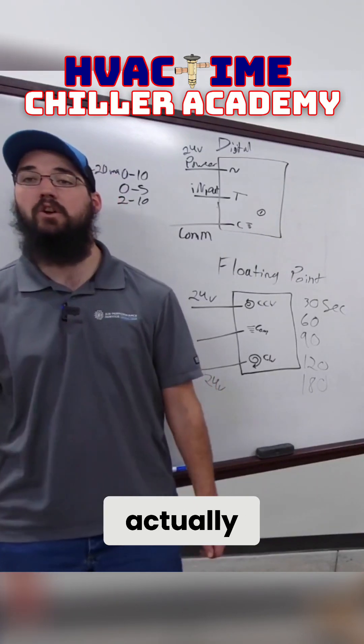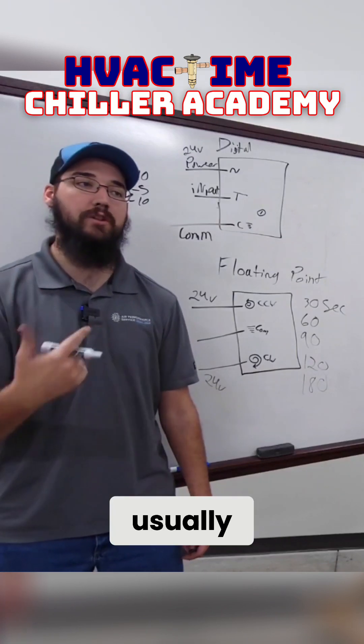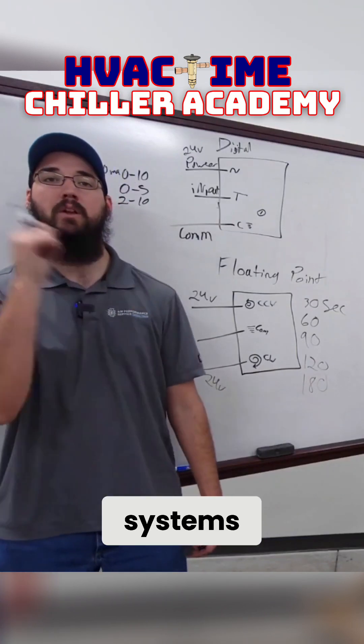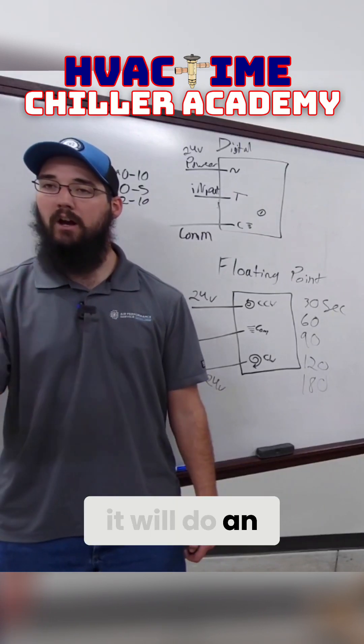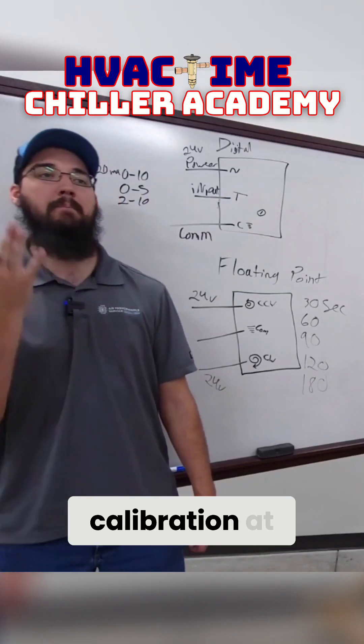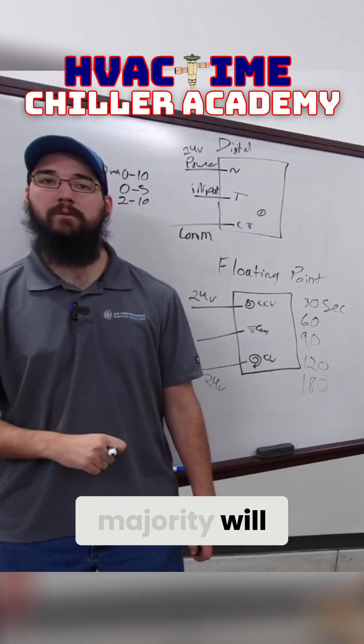And it doesn't actually know its real position. And so usually most of these systems, when you cycle power, it will do an automatic calibration at power up. Not always, but the vast majority will.